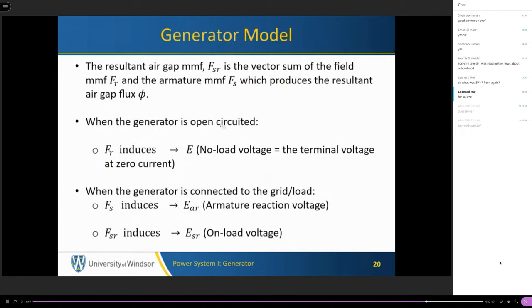When the generator is open, this is the first case, we have all of FR, which induces E. This E we call the no load voltage, the voltage that appears on the terminals of the generator when there is no load. So if the generator is like this, you have a breaker and you have the load or the power system, this is the network or the load. The voltage you measure here is going to be E when the breaker is open.